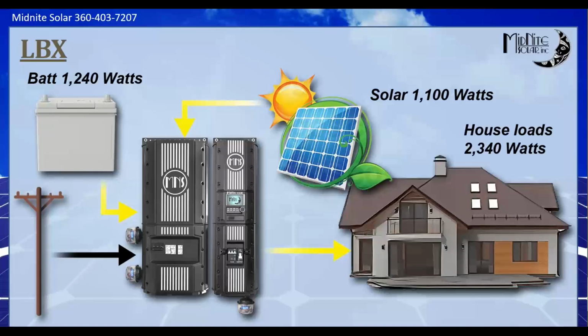When you've told it to ignore the grid, the Rosie will ignore the grid, and it needs some other steps if you want it to not ignore the grid during a low battery cutout or overload situation. The reason is that in time transfer, we're telling the Rosie to ignore the grid because we're presumably saving you from paying 2, 3, 4, 5 times your normal utility rate during peak demand time. The last thing we want is the Rosie reconnecting for whatever reason and using that grid, so we're setting it up so that's the absolute mode. Then if you want it to fall back over to the grid during an overload or low battery cutout, low battery cutout should be automatic, but for overload we have to enable what we call load transfer, which we'll talk about in a bit.